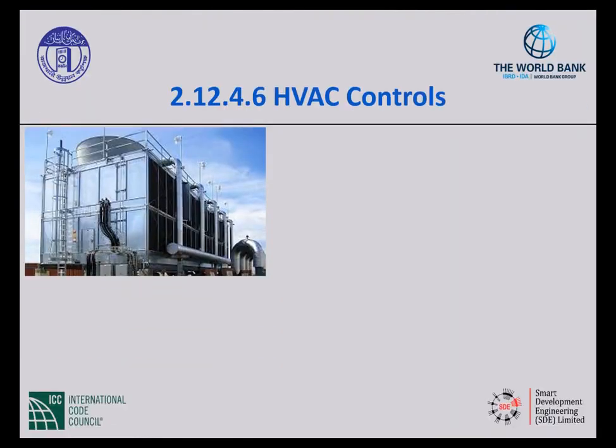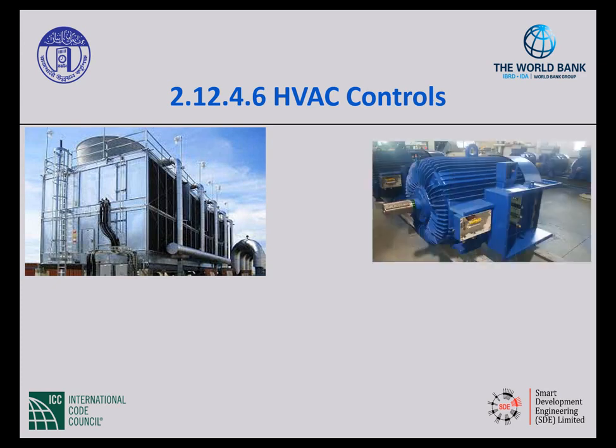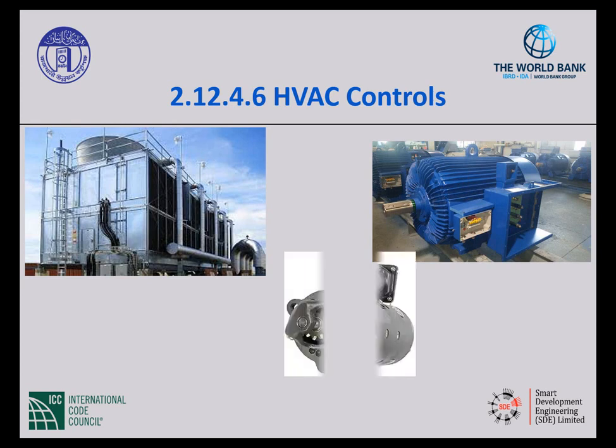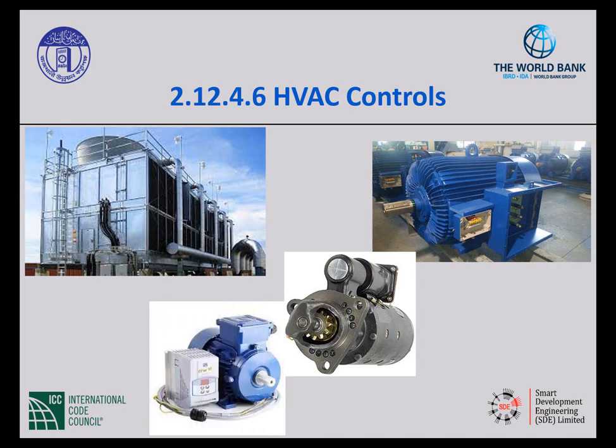And then it's asking that cooling towers and closed fluid coolers have either a 2-speed motor, a pony motor, if you've heard of that, like a backup motor, or a variable speed drive to control the fans. Those are big, huge fans on those cooling towers. And so it's just asking that we put some thought and consideration into what can be the most efficient way to run those fans.